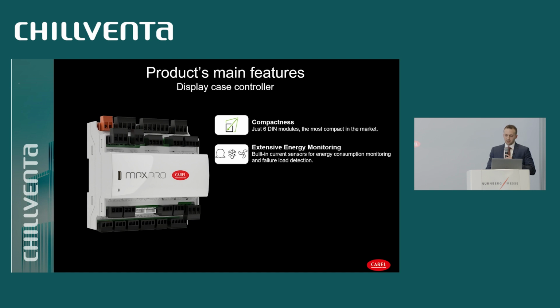Another important point is the comprehensive energy monitoring through built-in current sensors, up to 3, in order to detect load consumption, but also possible load failure detection. What we mean, for sure, if we think at a higher level, this kind of solution can easily detect the consumption of each load that is connected to the controller. And so we have the possibility to enable higher-level analysis, clusterization of consumption, and so on. But this also has the double effect that we can provide information on immediate load failure.